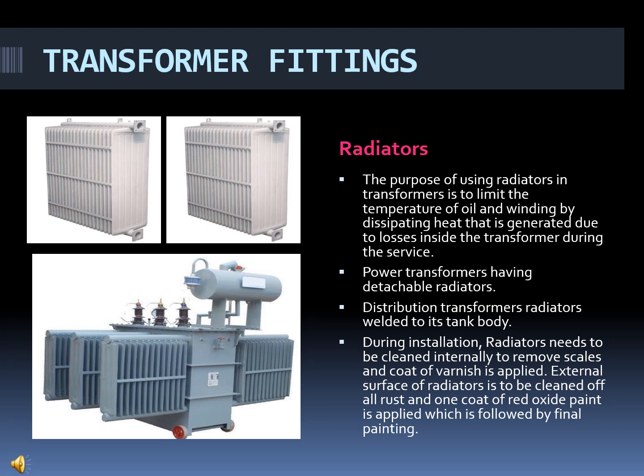Let's understand that during the installation phase, radiators need to be cleaned internally to remove scales, and a coat of varnish is to be applied. The external surface of the radiator is to be cleaned of all rust and one coat of red oxide paint is to be applied, followed by the final painting. This direction is to be used only during installation. If you want more detail about radiators, I have another video, enclosed in the description. Just look into the ONAN type of transformer, which is explained in detail for an oil natural, air natural type of transformer. You can watch it.